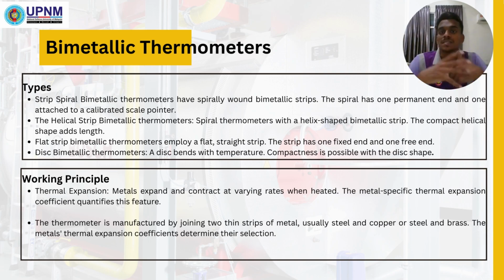So, how do bimetallic thermometers work? First off, it depends on thermal expansion. Metal expands and contracts at varying rates when heated. The second working principle is the thermometer is manufactured by joining two thin strips of metal. Most commonly used are copper, steel, or brass. The metal's thermal expansion coefficients determine their selection.